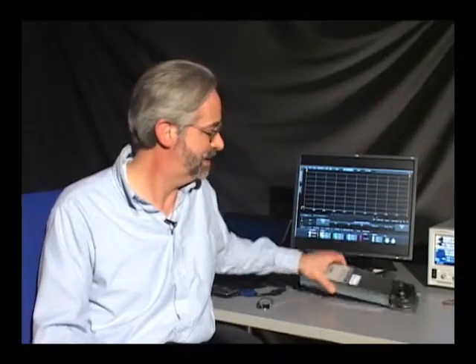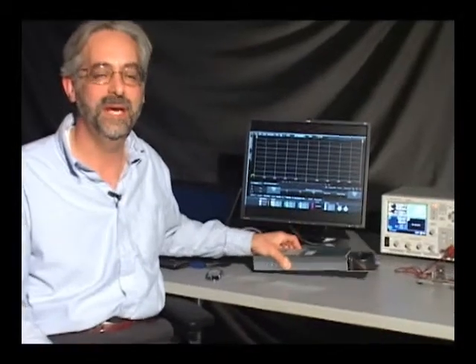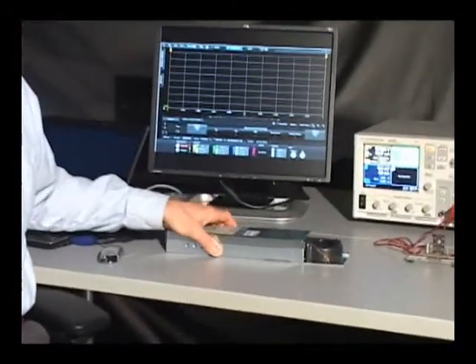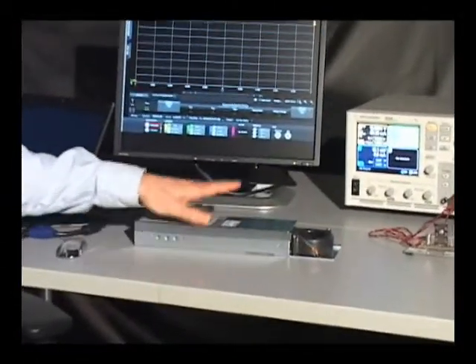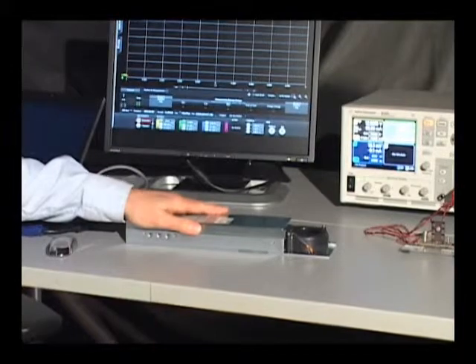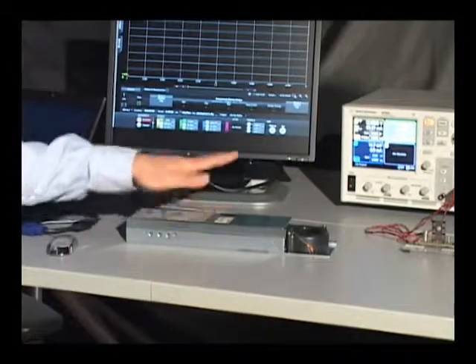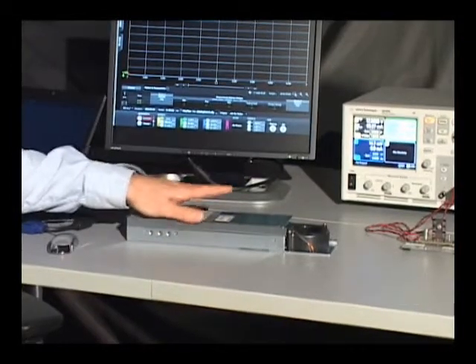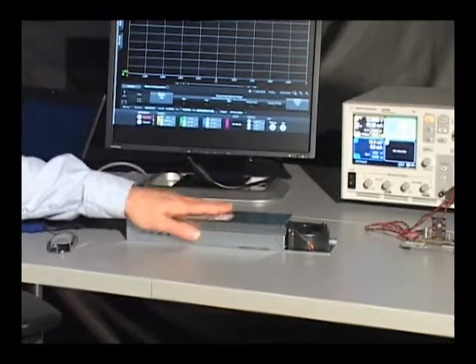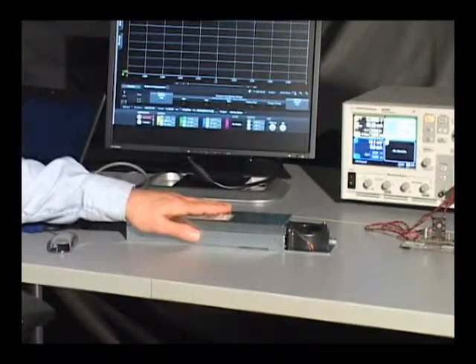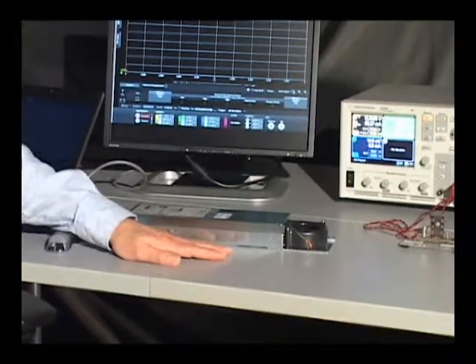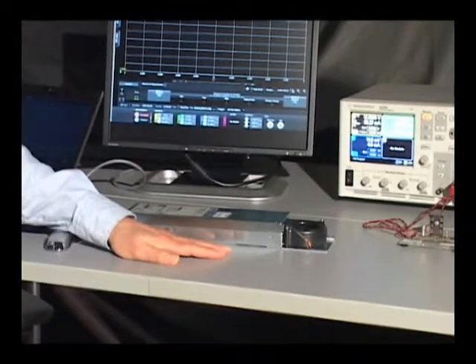This testing is made quick and easy using an N6782 source measure module for functional testing. This device can source and sink current, so it performs as both a source and electronic load for testing voltage regulators and other similar components.